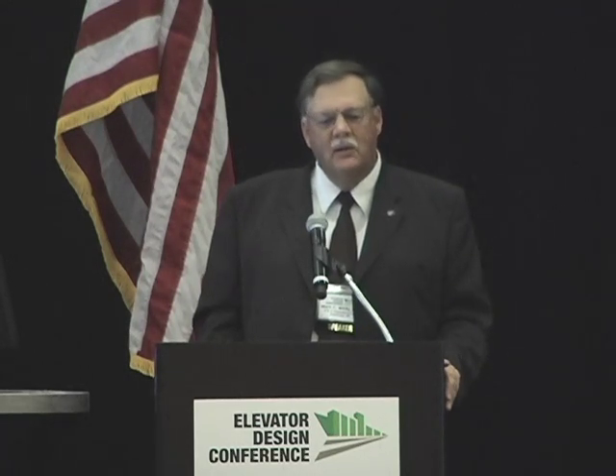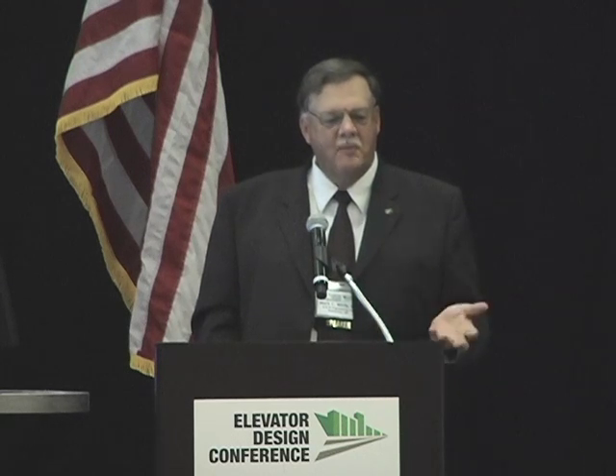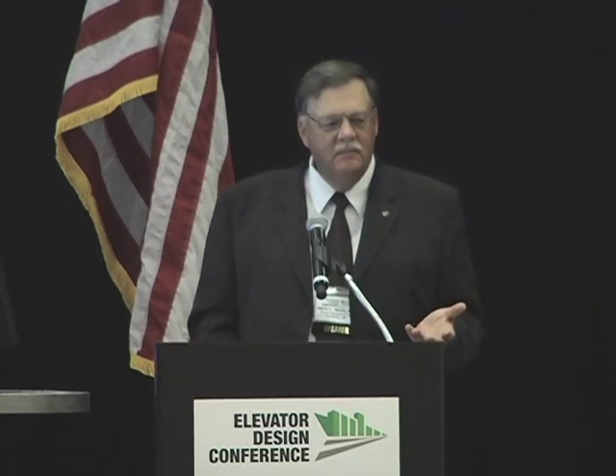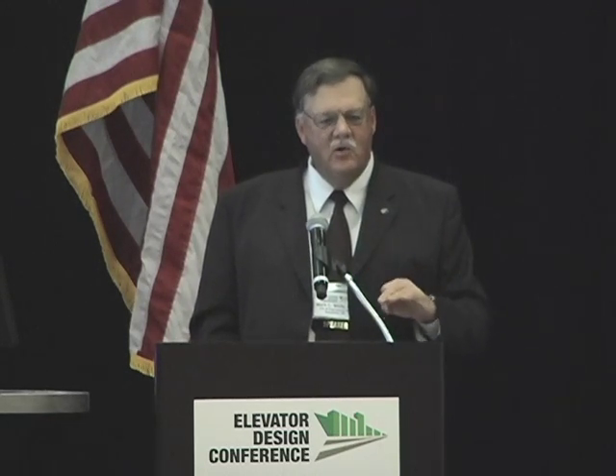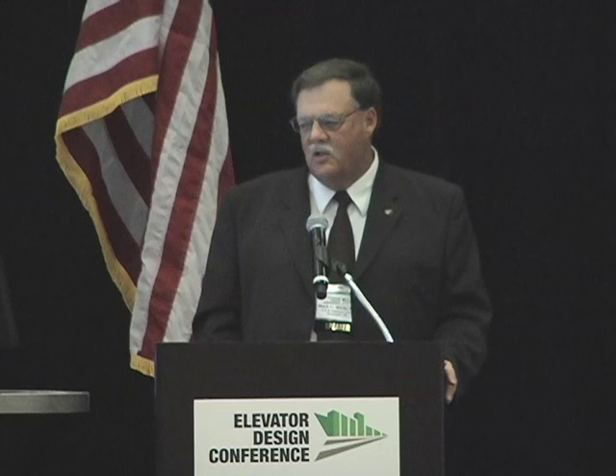Even with soft starters, there is a capability for some energy conservation. A lot of them have a control mode where when the motor drops back, if the conveyor is running empty, it actually drops back the excitation voltage slightly on the motor and reduces the actual energy into the motor and makes it run more efficiently when it's running at light currents. So you can actually get some energy conservation out of some of the soft starter technologies.